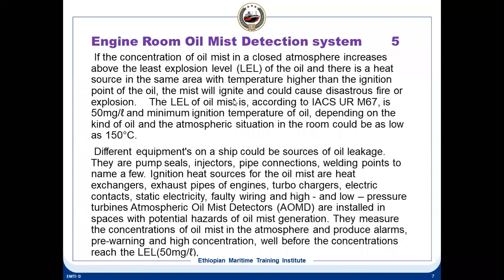It gives alarm in two different stages. One is a pre-warning alarm and the second is a high concentration alarm. So the pre-warning alarm you will get in the engine control room, telling you that yes, there is a minor leakage. So immediately you can attend to this and fix the problem. And the high concentration also will go to alarm.